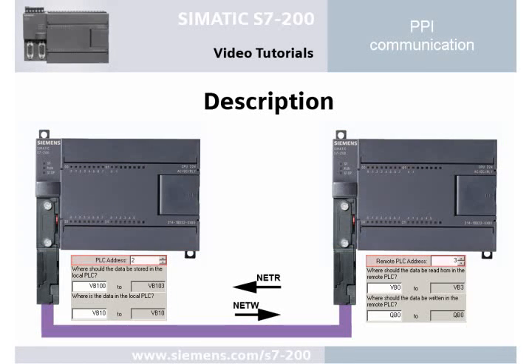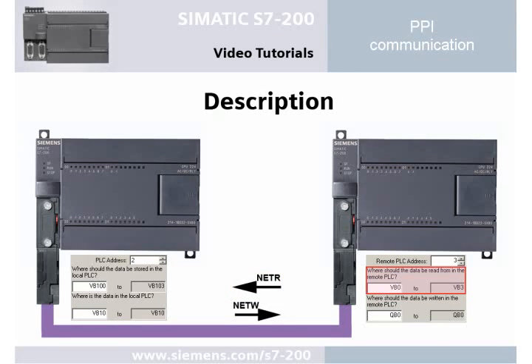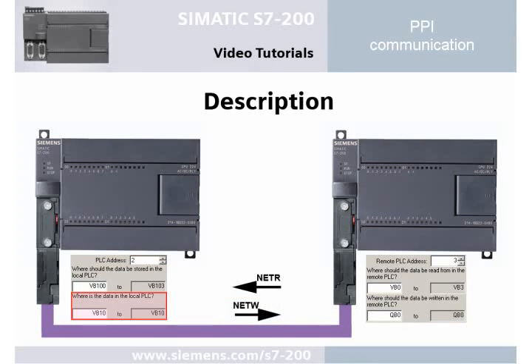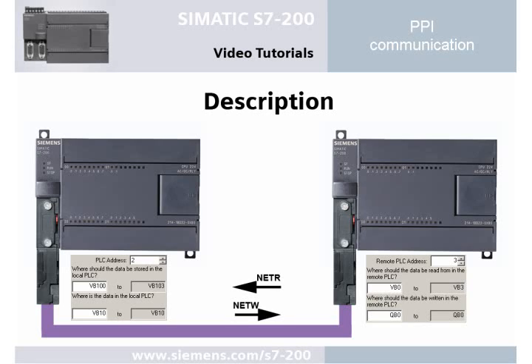The respective communication partner is identified via the address. Using the NetR function enables reading a data area from a remote PLC and storing it in a selected data area of the local PLC. Using the NetW function enables writing a data area from the local PLC into a selected data area of a remote PLC. This enables communicating with up to 24 PLCs via the instruction wizard for NetR and NetW.